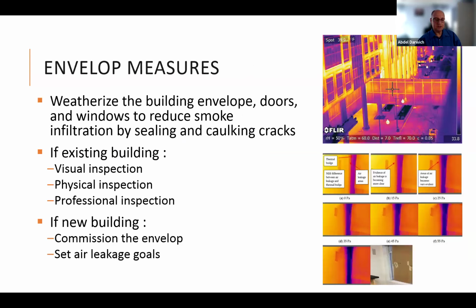The envelope. Again, the envelope is a way for wildfire smoke to get in. You need to weatherize the building and make sure that it's airtight. For an existing building, I usually recommend a visual inspection, which is usually just you walk in and you see daylight. Yeah, that's a gap. You can also take it to the next level and do a physical inspection, where you pressurize the building with fans and see whether the building holds the pressure. It's like checking the pressure in your tire: you pressurize it, put it in water, and see if there are bubbles. That's basically what you're doing.